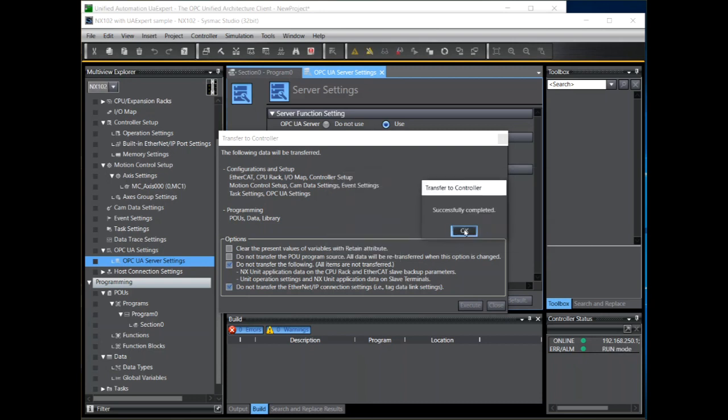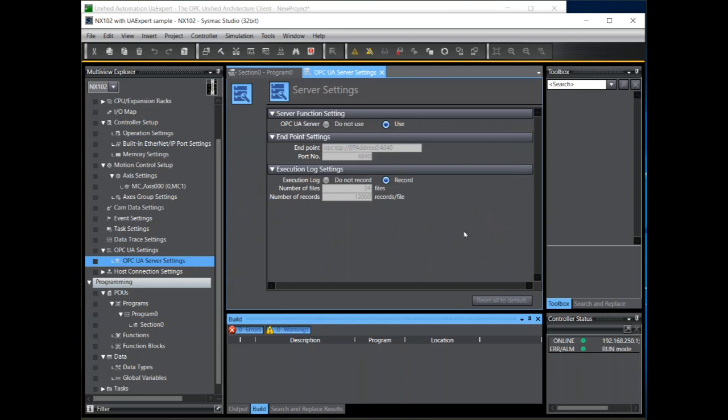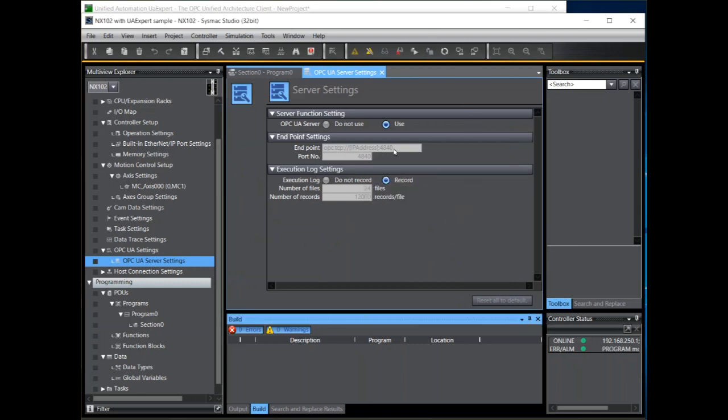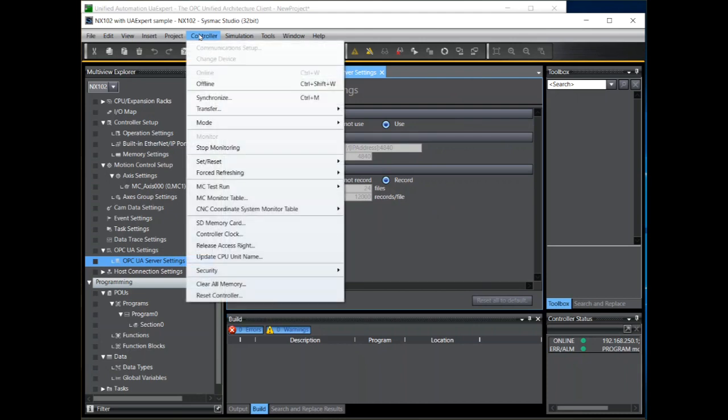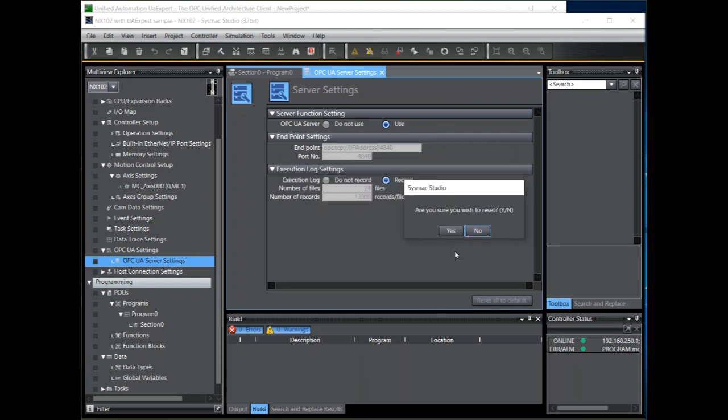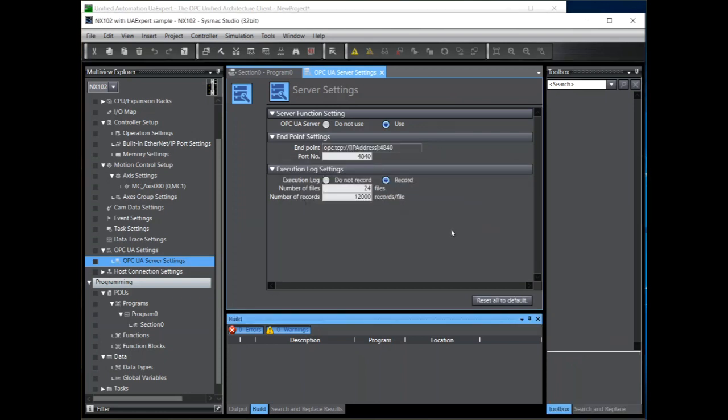To reset the controller from Sysmac Studio make sure the controller is in program mode. Then from the controller menu select reset. Note that Sysmac Studio automatically comes offline as the NX102 reboots.